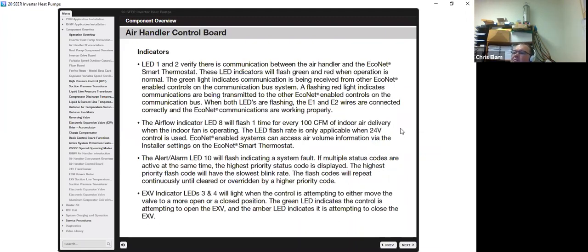The indicators on the unit, LED 1 and 2, verify if there is communication between the air handler and the EcoNet smart thermostat. If you don't have communication, you're going to know it ahead of time because you're going to have an error code. These indicators will flash green and red when operation is normal. The green light indicates communication is being received from other EcoNet enabled controls on the EcoNet communication bus system. A red light indicates the communications are being transmitted to the other EcoNet enabled controls. When both LEDs are flashing, E1 and E2 wires are connected correctly and the EcoNet communications are working properly.